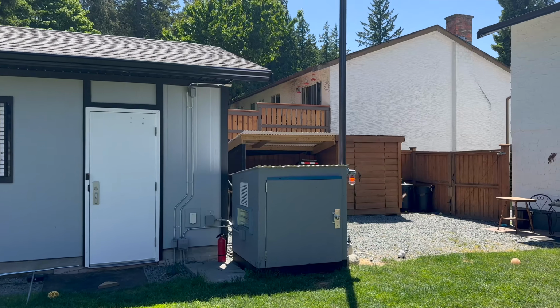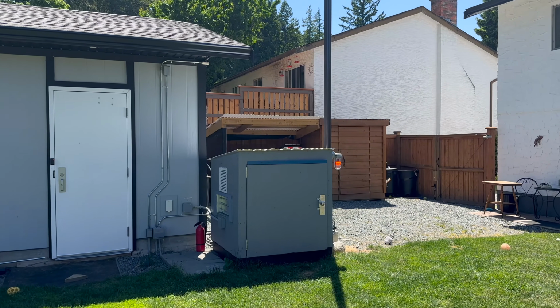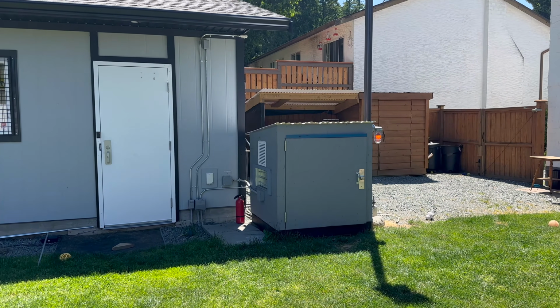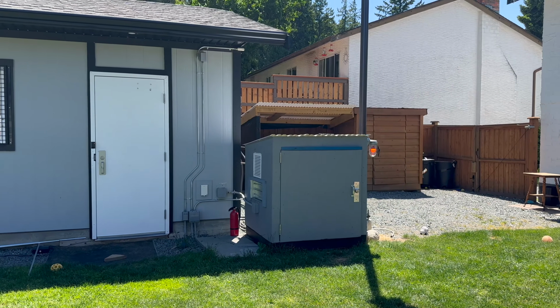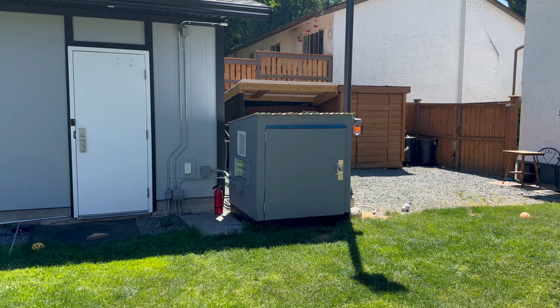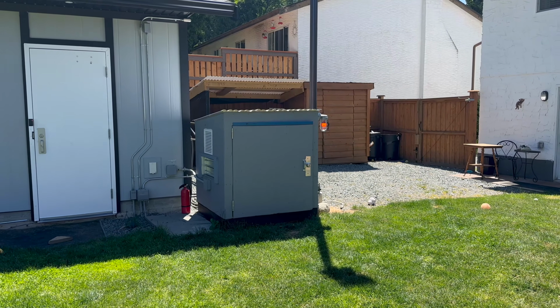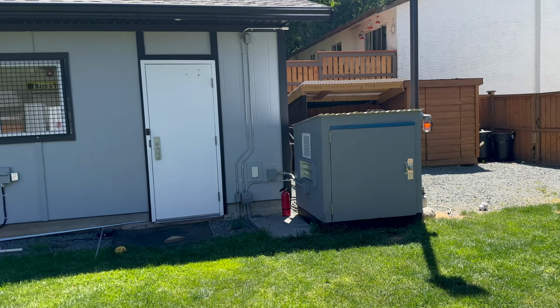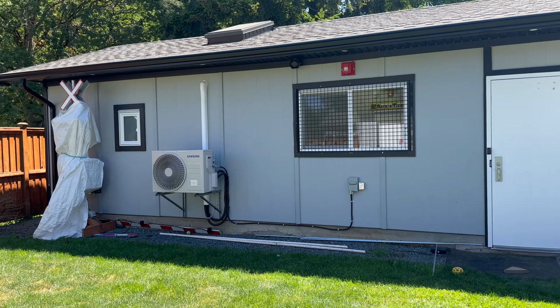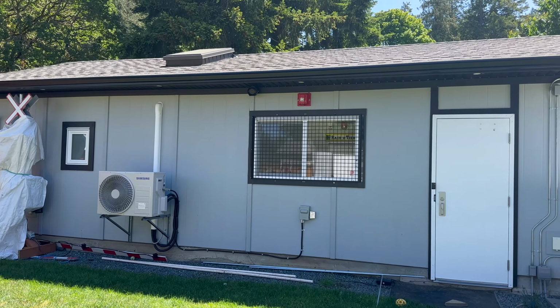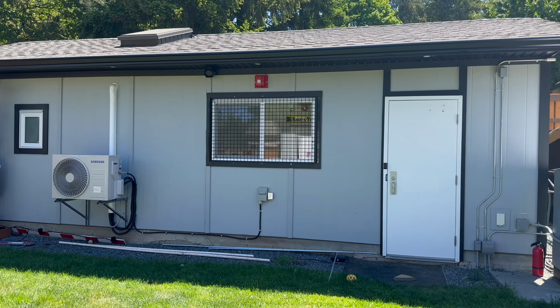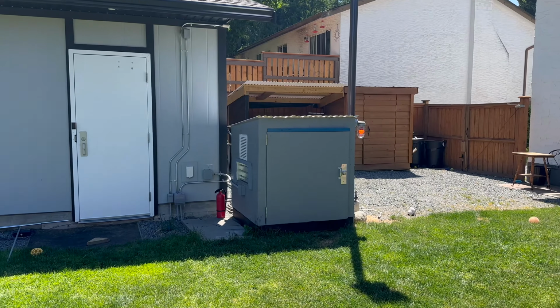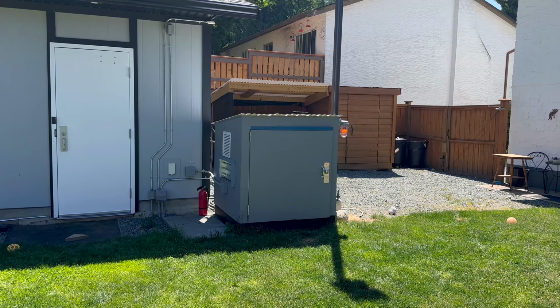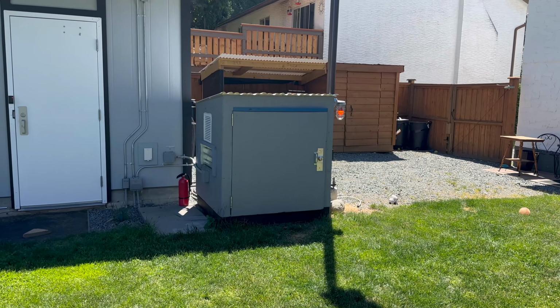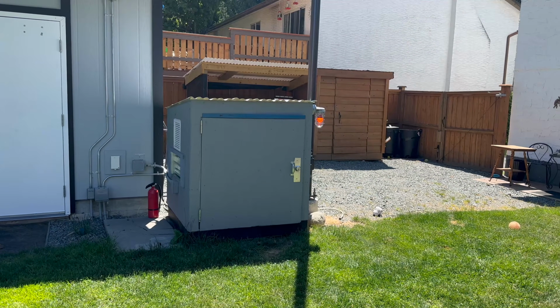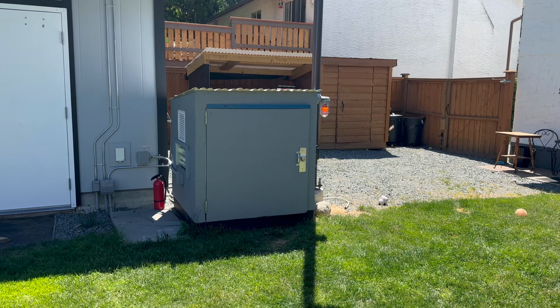This should give me around 12 hours of runtime on generator at 50%, though usually the generator is run much less than 50%. Usually we're not over 20% of the generator's fully rated load, as the heating load of this building is very efficient with the heat pump as well as all LED lighting. The load is never too much. The only load that puts significant load on the generator is the hot water tank, which does not turn on very often. So we should realistically get around 16, 17 hours out of the generator.